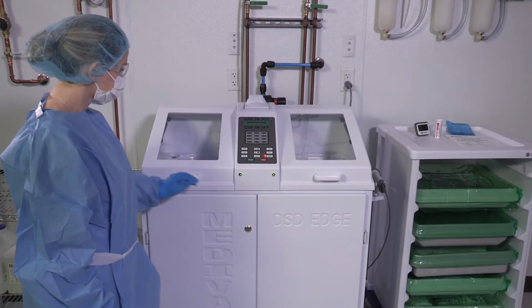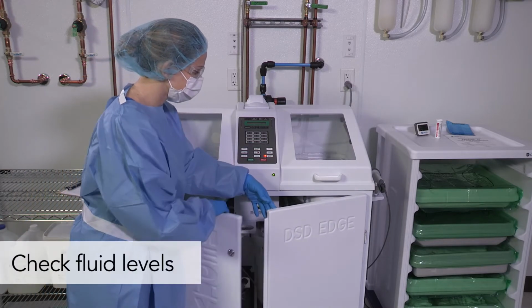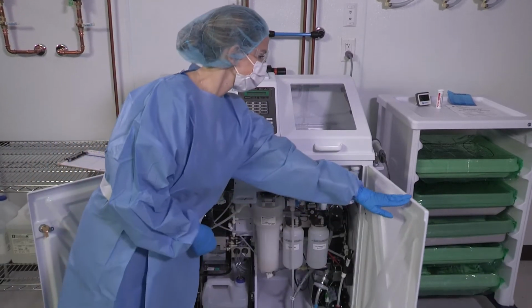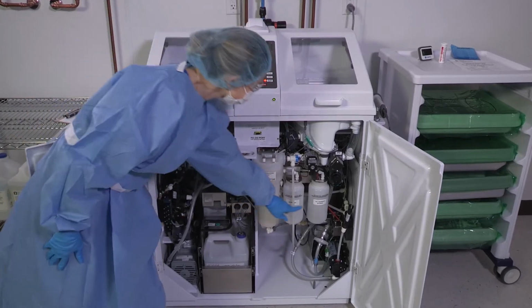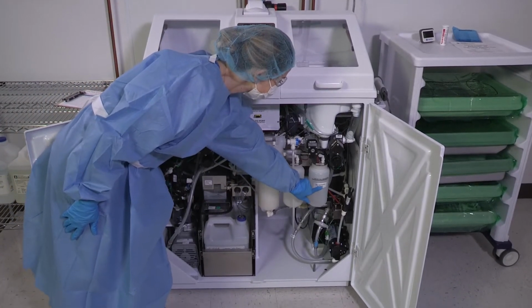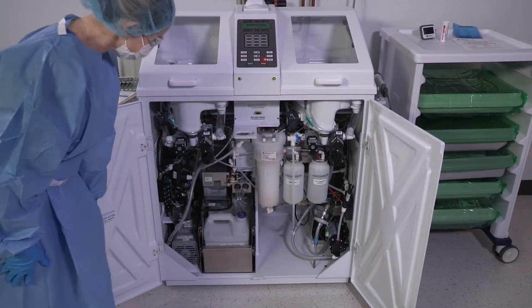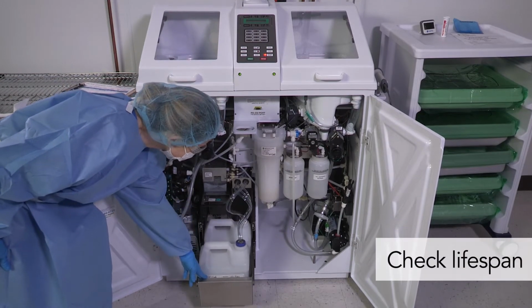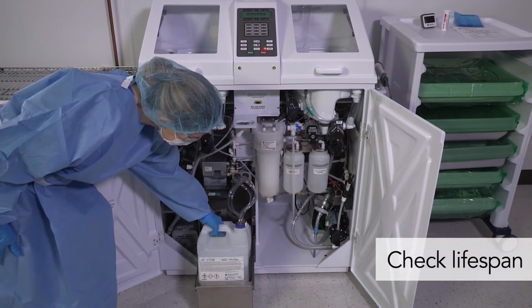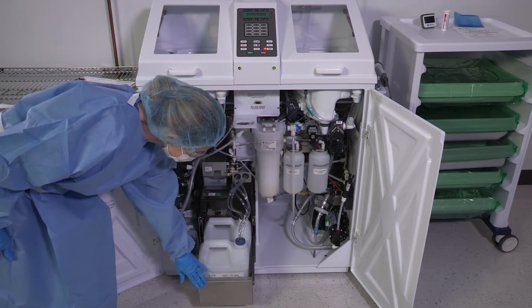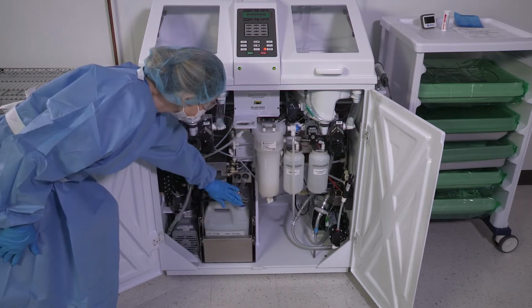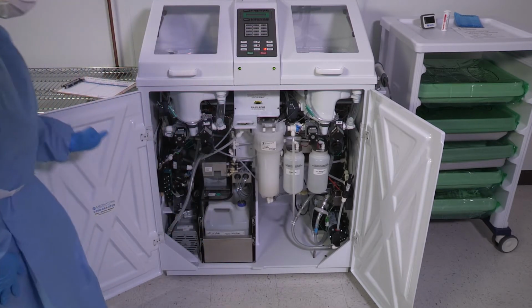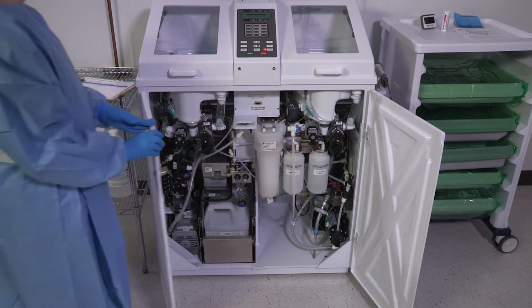Open the doors to inspect the alcohol fluid level. If using detergent, check the detergent reservoir level. If fluids need to be replaced, review the loading fluids segment. Ensure Rapicide PA disinfectant parts A and B are within their usable lifespan, which is 21 days after opening or prior to the expiration date on the containers.